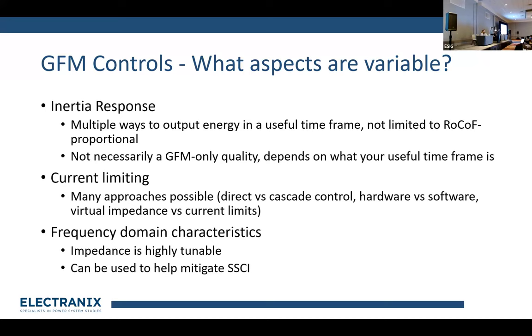The last variable aspect is the frequency domain characteristic. From experience doing sub-synchronous control interactions, the impedance that inverters have in the sub-synchronous frequency range is tunable based on the gains of the device — and that's the same case for grid forming. There's potential to tune the gains to get more damping at certain frequencies if we're seeing instabilities, which could be used to mitigate sub-synchronous control interactions in highly series-compensated systems.